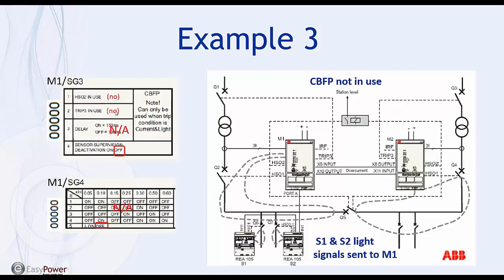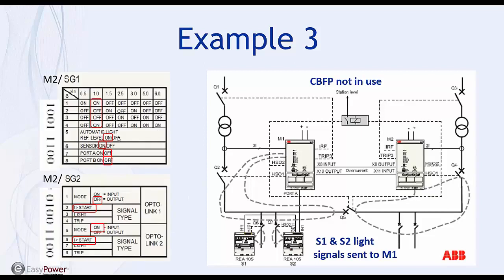We're not using breaker failure for Q1, and we are supervising the loop. We're not using the ground, so that's turned off. For main 2, same thing, 1 amp per unit nominal, using backlight compensation, activating the sensor, and we're not connecting any extension units to main 2. The OptoLinks we are using in conjunction with main 1, so here it's going to be just the opposite of what main 1 was. We're going to transmit on X8 on OptoLink 1, and we're going to receive on OptoLink 2, which is X11. We're going to pass that current information back and forth.